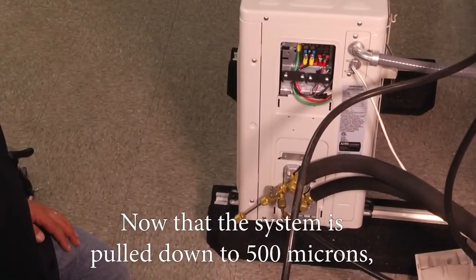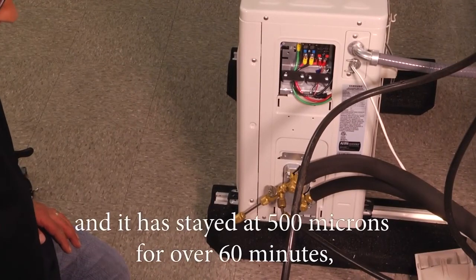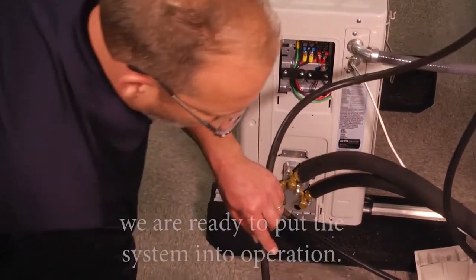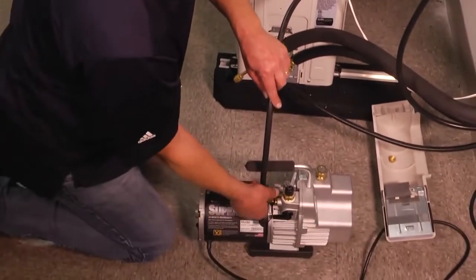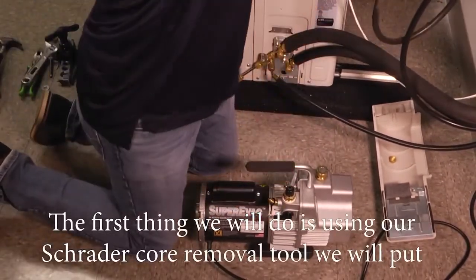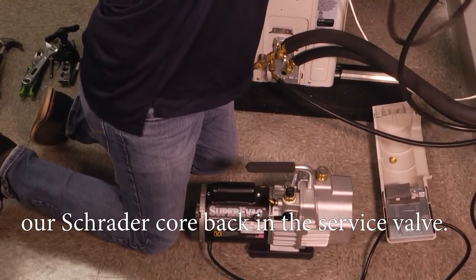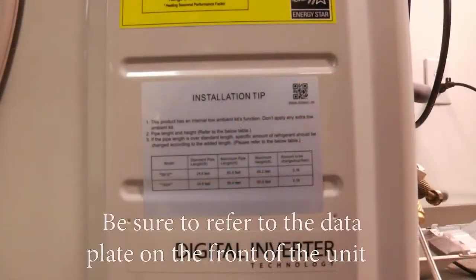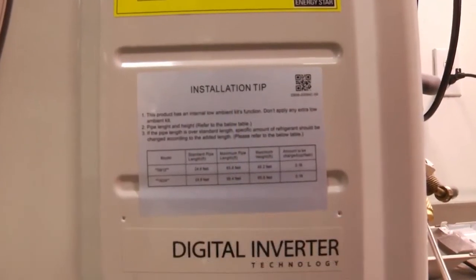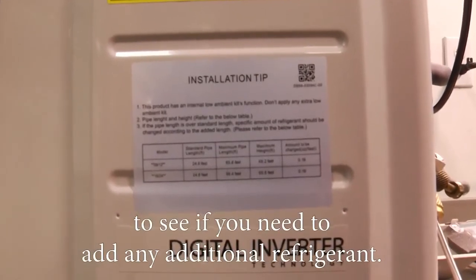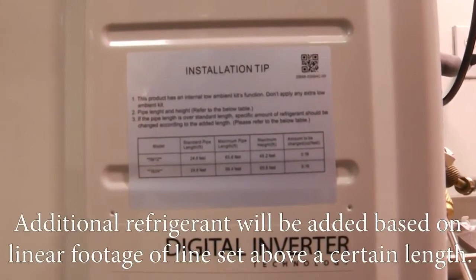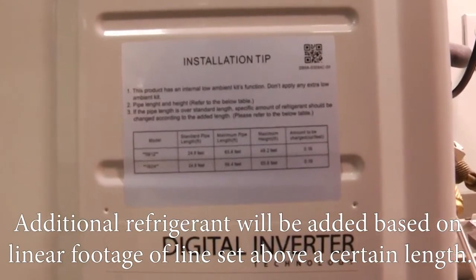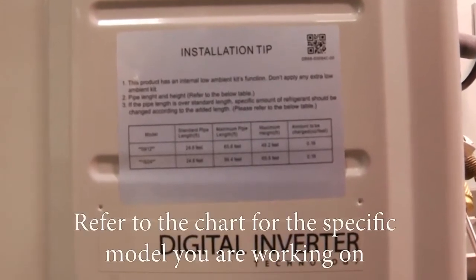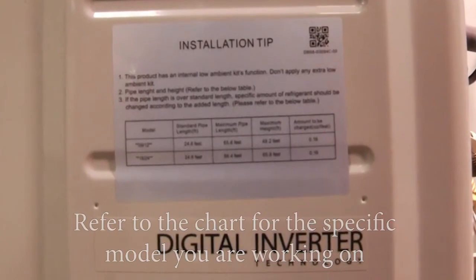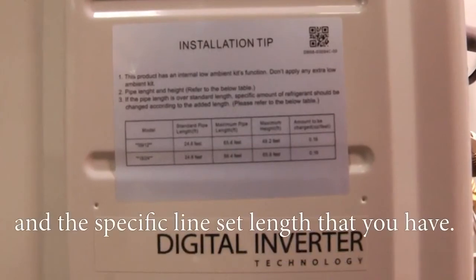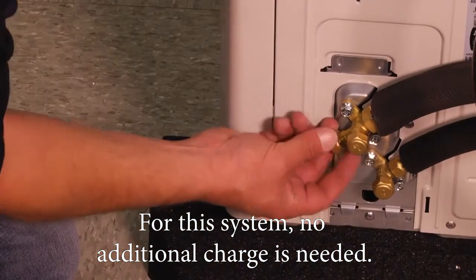So now that the system's pulled down to 500 microns, and it's stayed at 500 microns for over 60 minutes, we're ready to put the system into operation. The first thing we'll do is, using our Schrader core removal tool, we'll put our Schrader core back in the service valve. Be sure to refer to the data plate on the front of the unit to see if you need to add any additional refrigerant. Additional refrigerant will be added based on linear footage of line set above a certain length. Refer to the chart for the specific model that you're working on and the specific line set length that you have. For this system, no additional charge is needed.